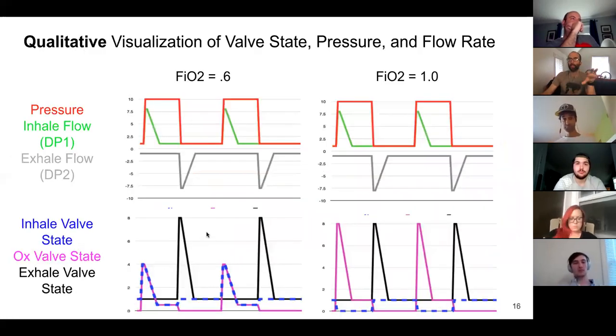So what that looks like from a data context is this. Let's say the pink line is the oxygen valve state, and the blue dashed line is the air valve state. So for FiO2 of 0.6, they're both going to open and close together. Now, what they do during exhale is going to be different to try and conserve oxygen. In FiO2 of 100%, the pink valve is going to open fully, the oxygen valve is going to open fully, the air valve is going to close fully.